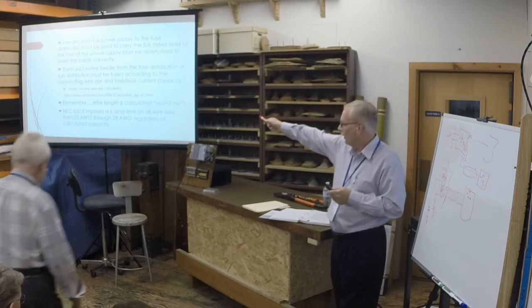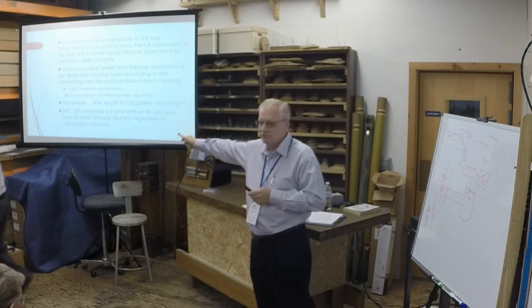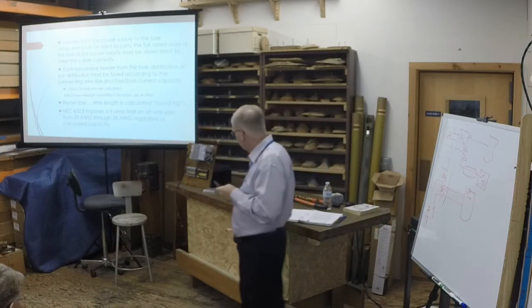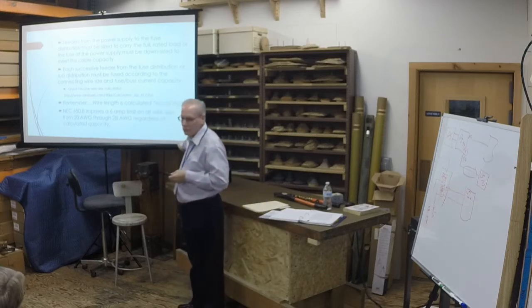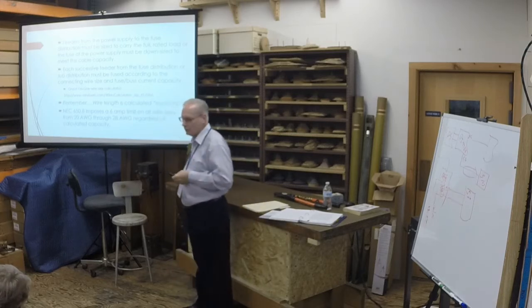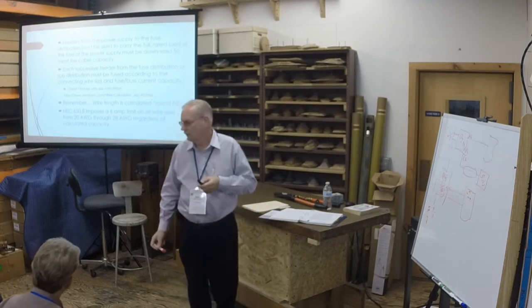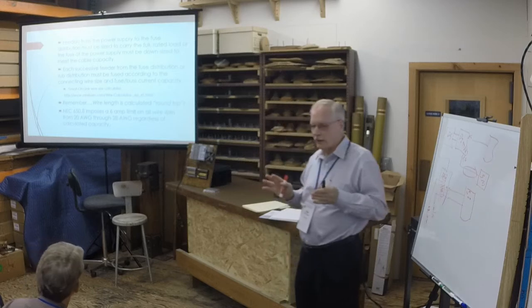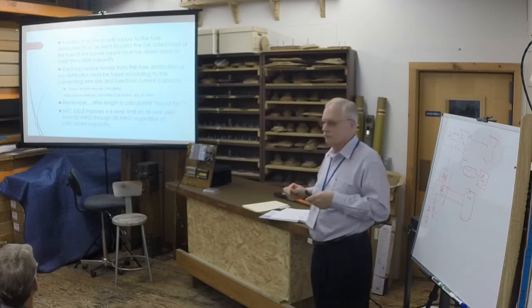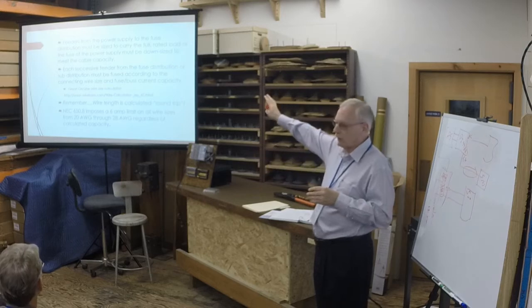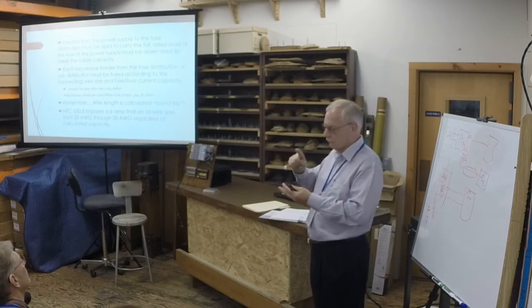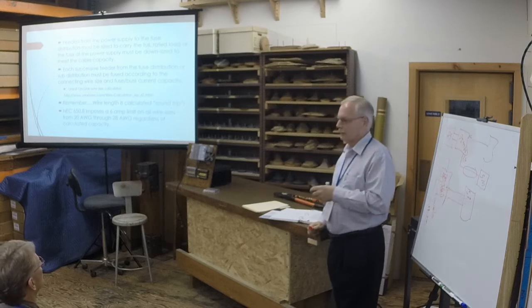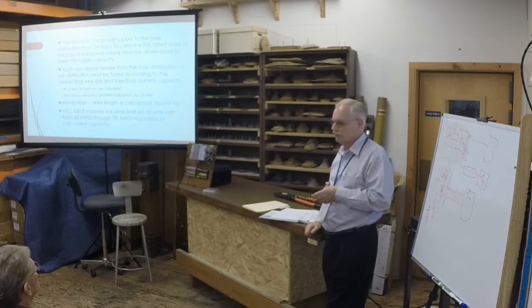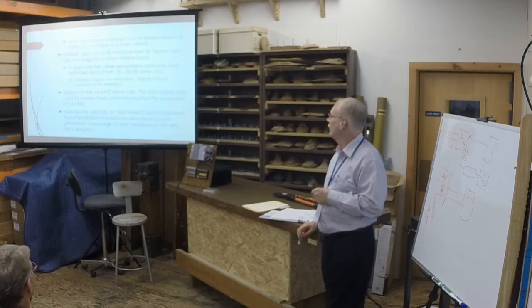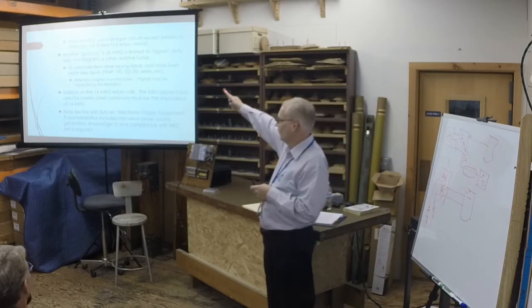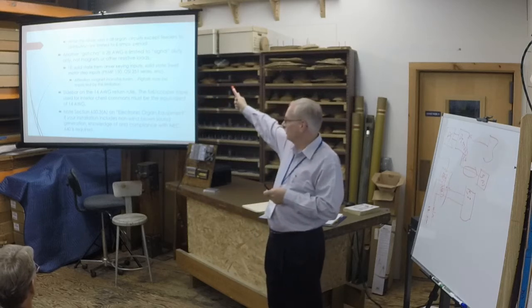Remember, wire length is calculated round trip, both directions. So that's 2 feet there in the grand scope of life, not 1 foot. You need to bear that more in mind for feeders. The organ, they've set the parameters for the organ. 6 amps, 14 gauge return, okay? And that pretty much covers whatever you're going to do out there. There we go. What it says, 6 amps period, no more.